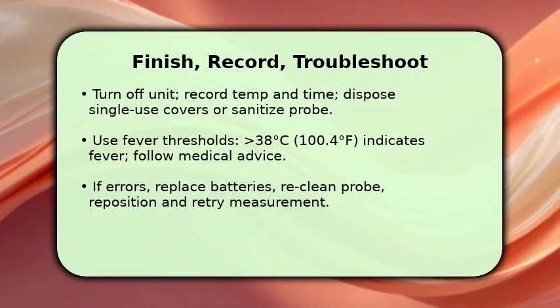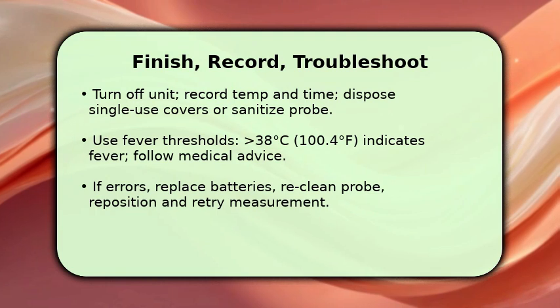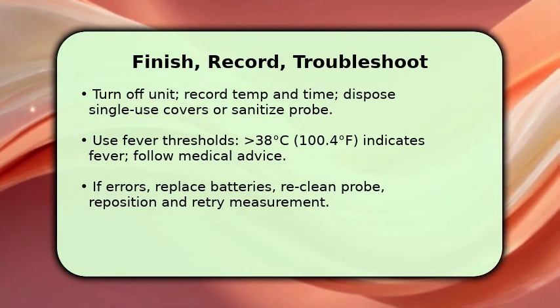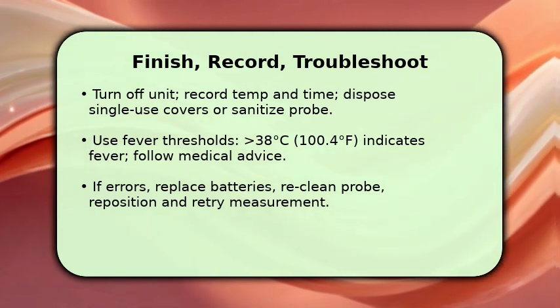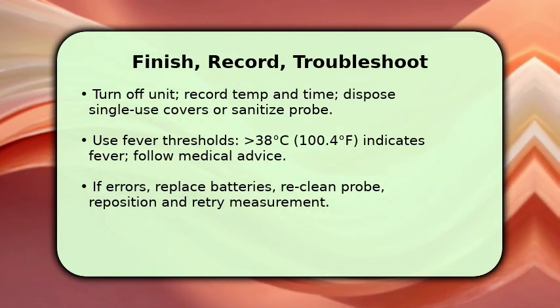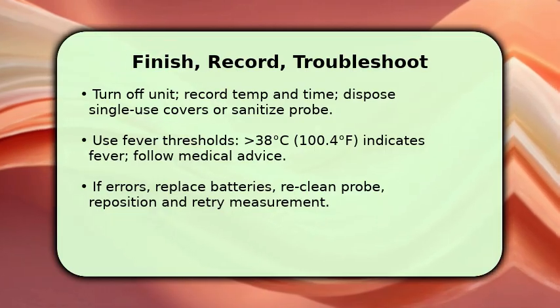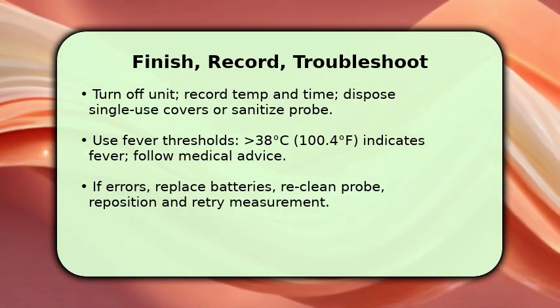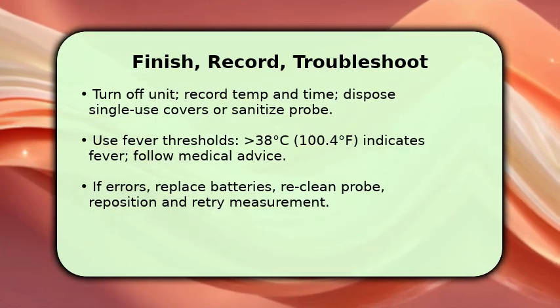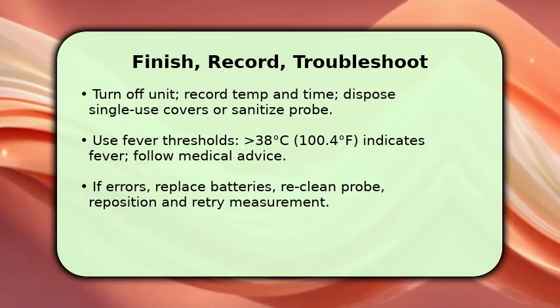After reading, switch the thermometer off and record the value and time for tracking. If you use disposable probe covers, discard them, otherwise sanitize with alcohol and let dry. Remember that readings above 38 degrees C or 100.4 degrees F typically indicate fever and warrant medical guidance.